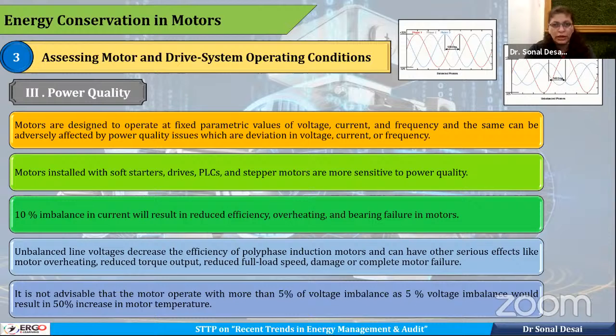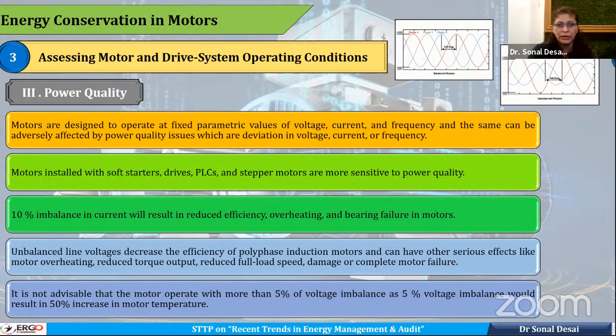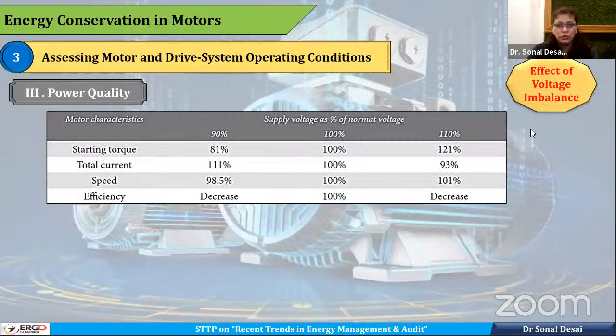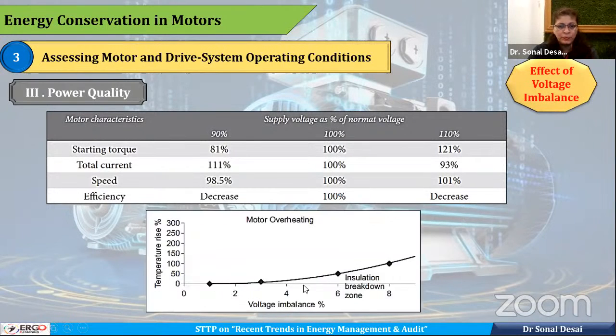Here, the effect of power quality is shown. When there is a power change, there is an effect on the starting torque, as well as an effect on the speed, that is shown in this table. Again, whenever an imbalance is created, temperature increases and heating of the motor takes place.